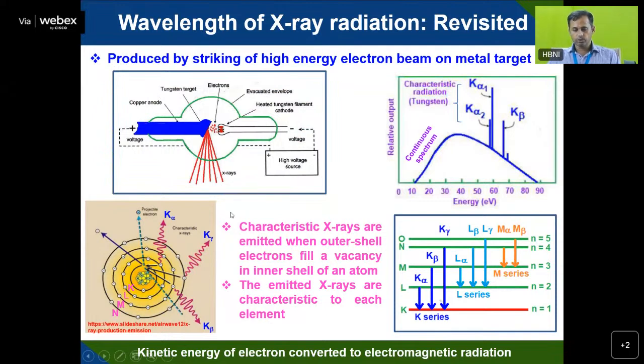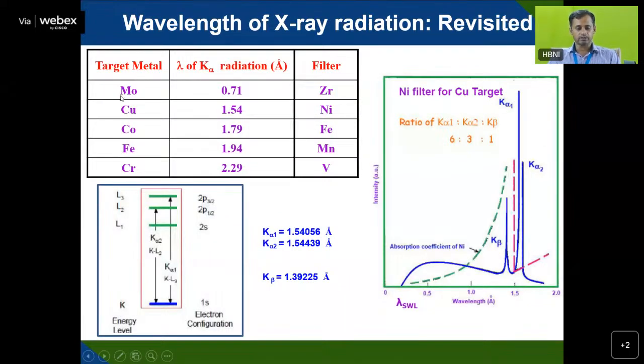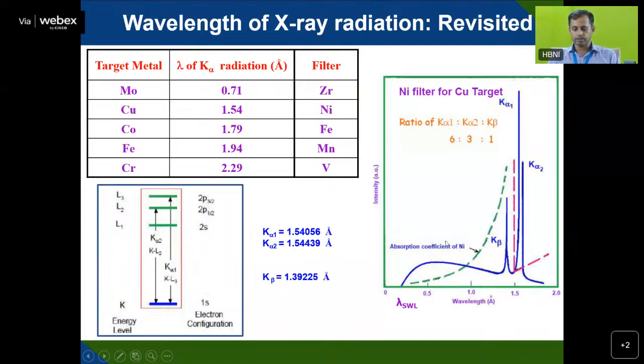You can see the wavelength of X-ray radiation for various targets: molybdenum gives 0.71 Å, and copper K-alpha gives 1.54 Å. These wavelengths are roughly equivalent to atomic D-spacing. The respective filters are one atomic number below the target: zirconium for molybdenum, and nickel for copper.